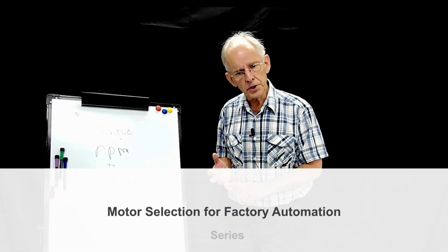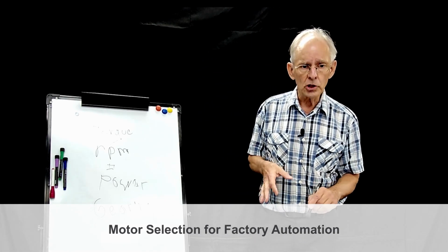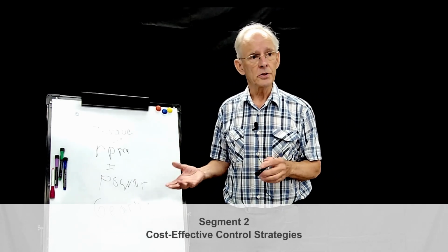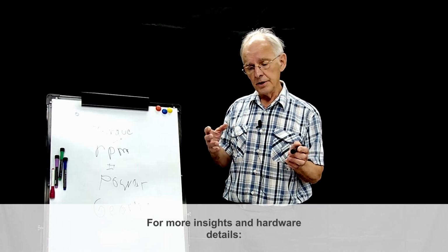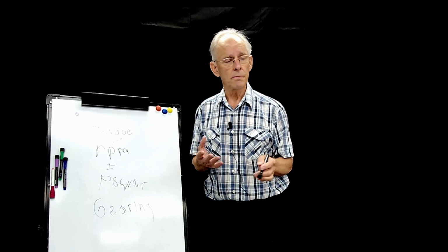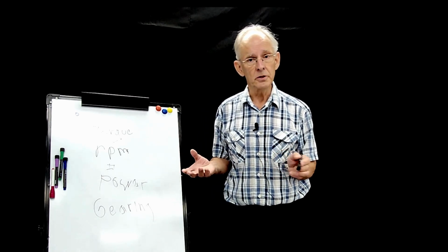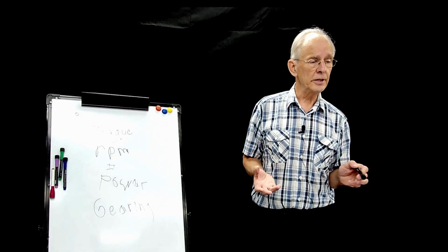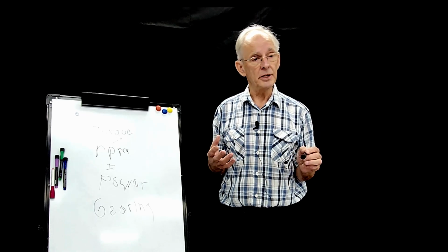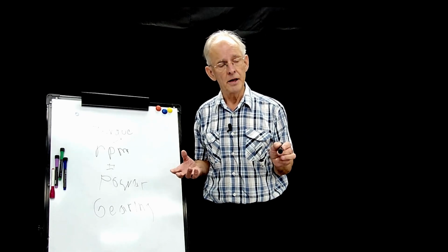All of the different motor technologies have a different cost associated with them, and there's usually a two-part cost. There's the cost of the motor and the cost of the control. Now in the case of an AC motor that's running at a constant speed, you're talking a contactor, which simply turns the power on and off to the motor. And that's relatively inexpensive, and again, that's real common in conveyors and that type of thing.